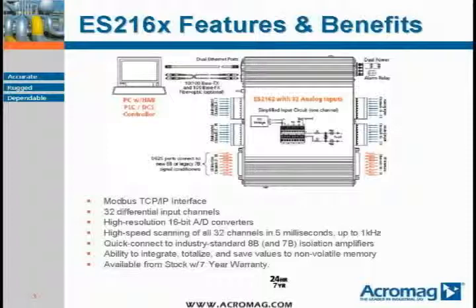High channel density also allows for fewer IP addresses and faster polling and scanning on all 32 channels. Channels may also be turned off in groups of 4 to allow for even faster polling cycles. One 4-channel group is scanned in just 760 microseconds, while all 32 channels are scanned in just 5 milliseconds. Industry standard 8B and backwards compatible 7B isolation amplifier connectors allow for up to 1500 volts of individual channel isolation in applications with electrically harsh or high voltage conditions.